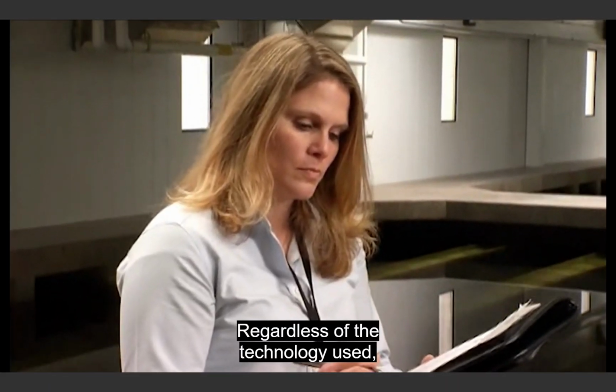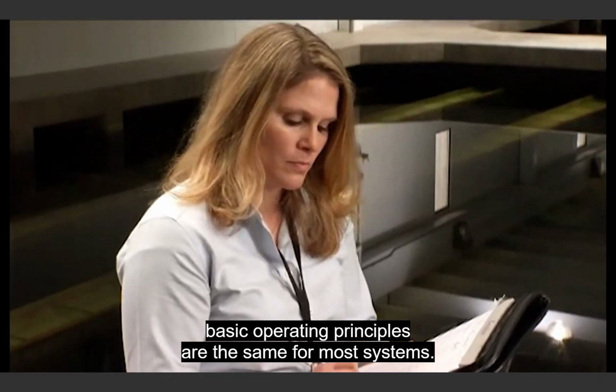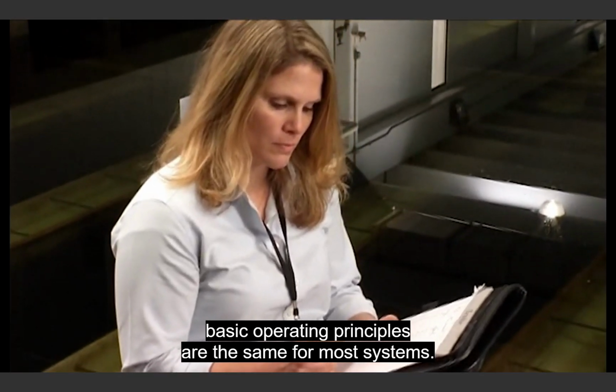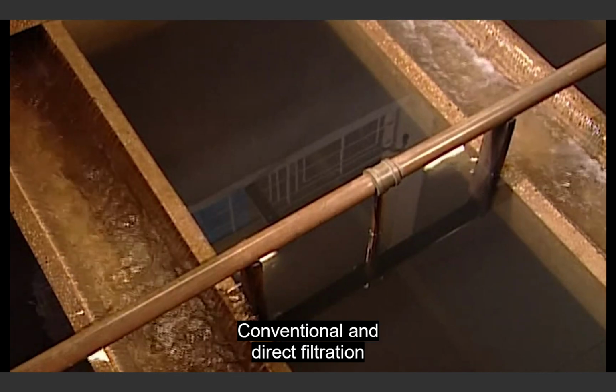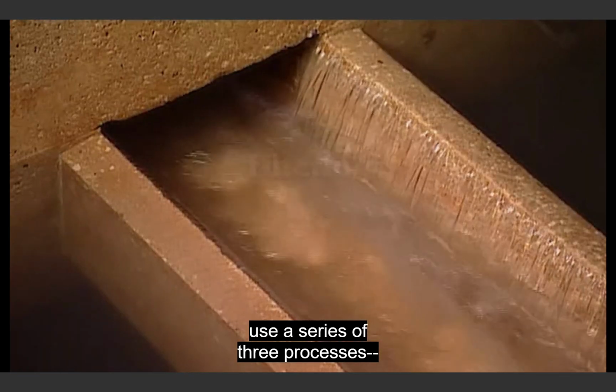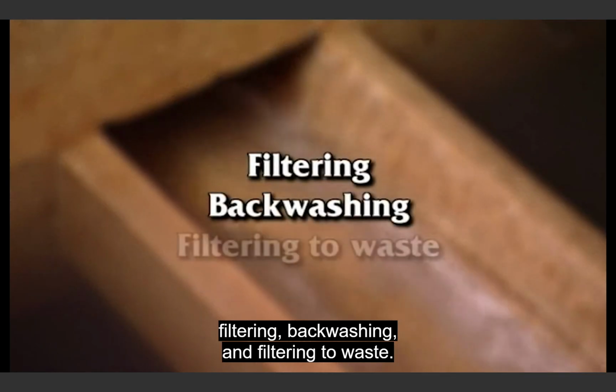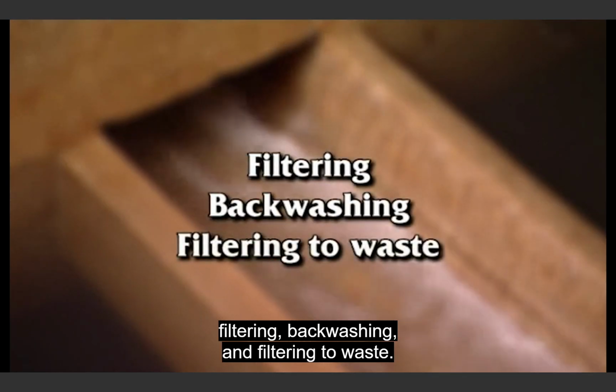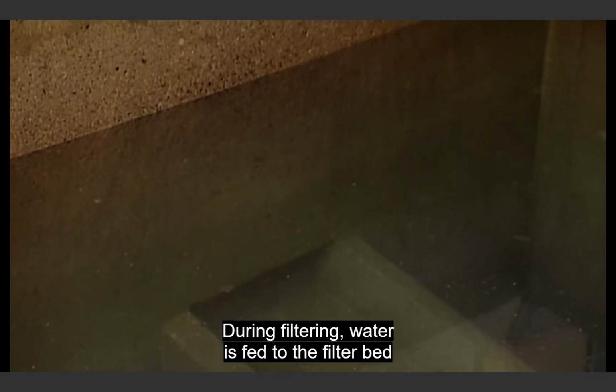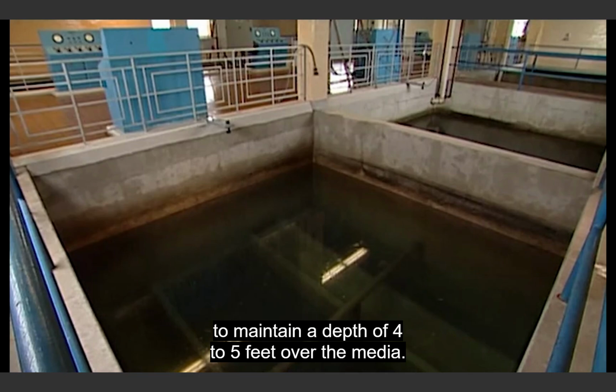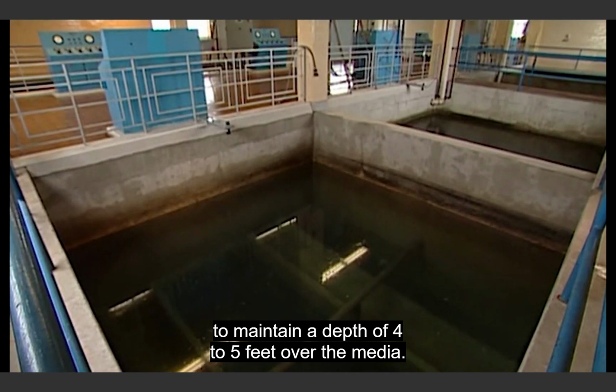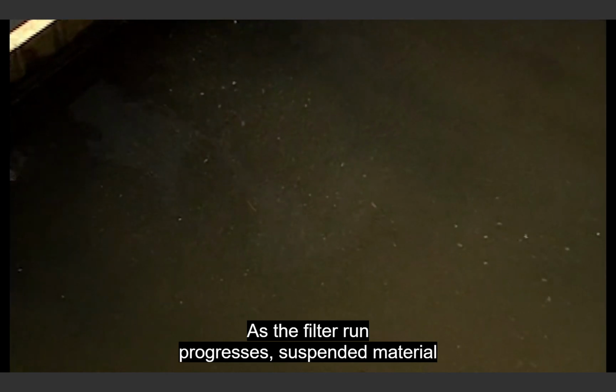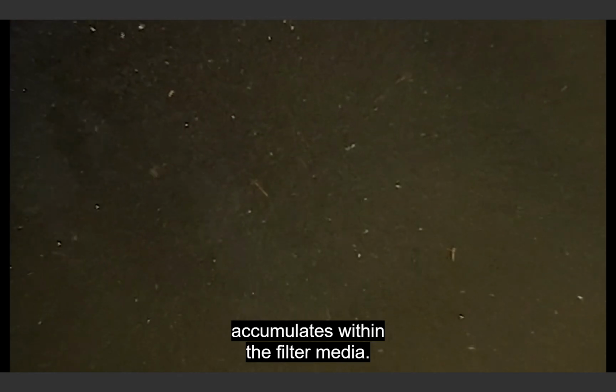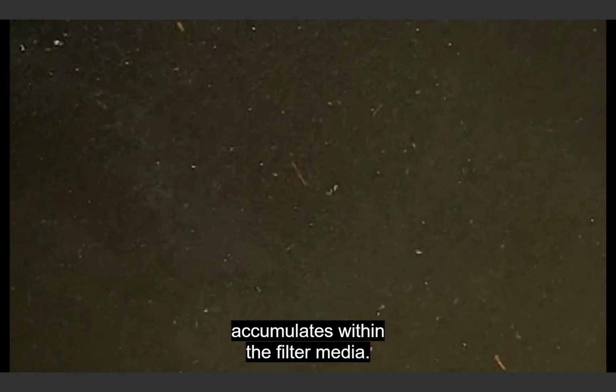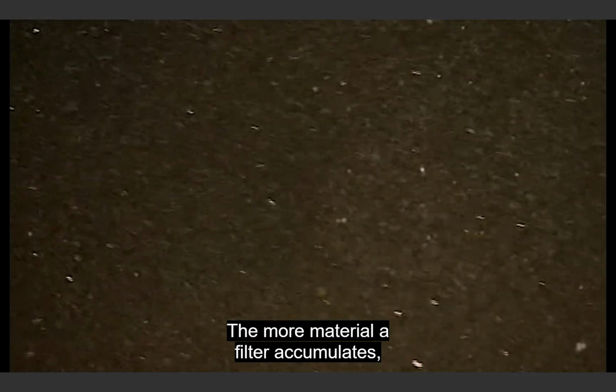Regardless of the technology used, basic operating principles are the same for most systems. Conventional and direct filtration use a series of three processes: filtering, backwashing, and filtering to waste. During filtering, water is fed to the filter bed to maintain a depth of 4 to 5 feet over the media. As the filter run progresses, suspended material accumulates within the filter media.